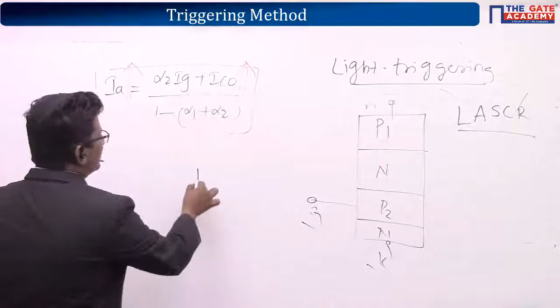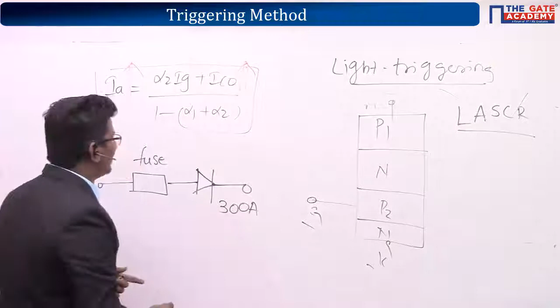Suppose I have a diode whose transient current is 300 amperes. To operate this device safely, how are we going to design this fuse? Do you want to choose a current equal to 300, more than 300, or less than 300? You have to choose a fuse which is less than 300. It means your fuse I square T heating effect should be chosen at only 200 amperes.